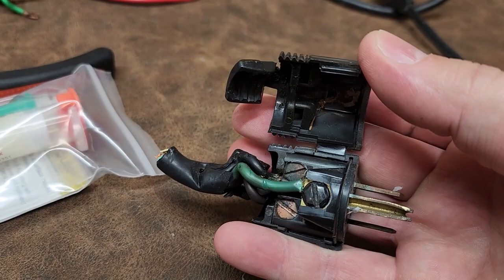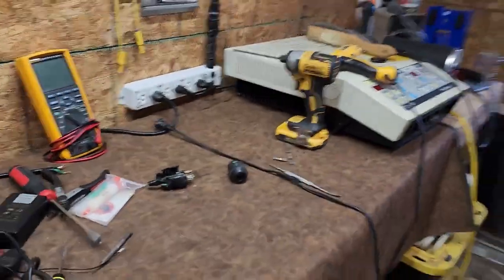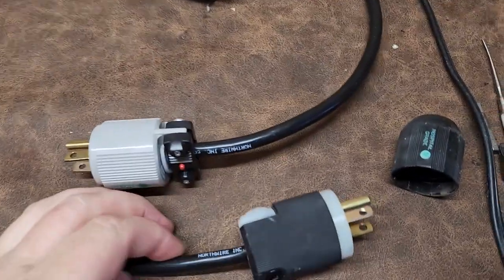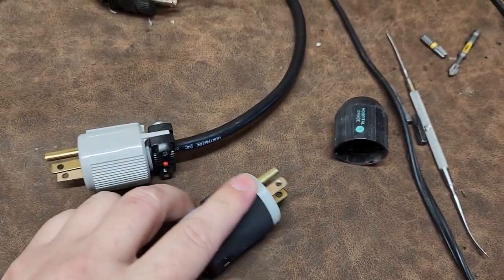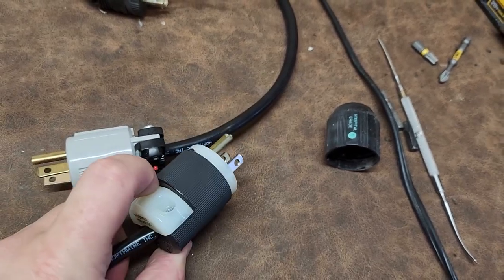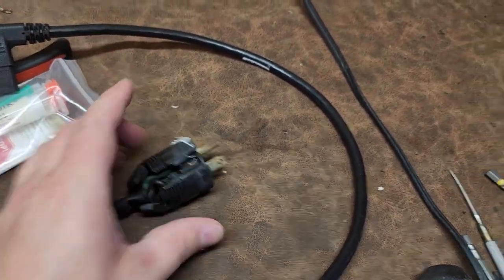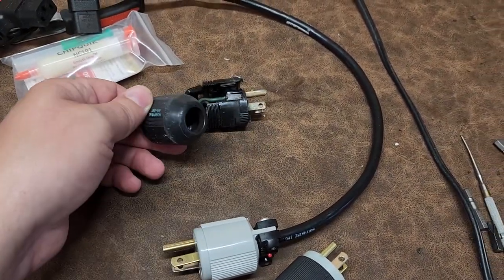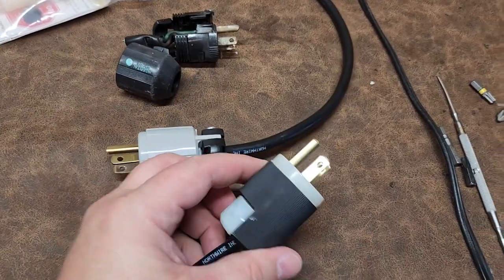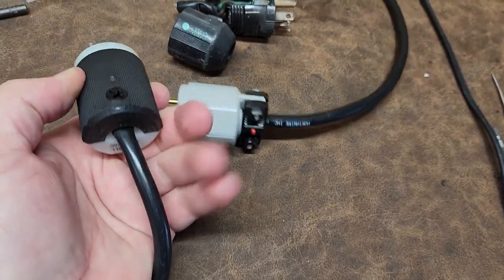I didn't reuse it — I already said I disliked those kinds of connectors, and I had better options. One of my better options was Hubbell. This style right here is a hospital grade plug, and notice how it's kind of sealed from the elements. Whereas this one has all those points of possible entry for fluid and moisture, even on the back — it was definitely not the correct plug-in for being outside. This Hubbell plug has a lip that seals it much better, and the crimp is much better too.